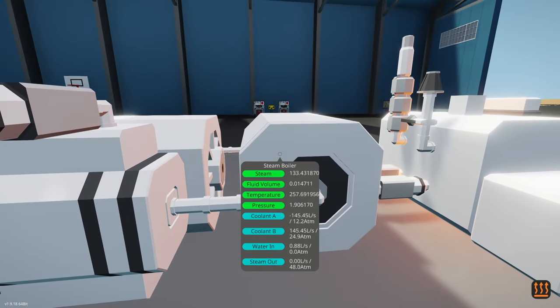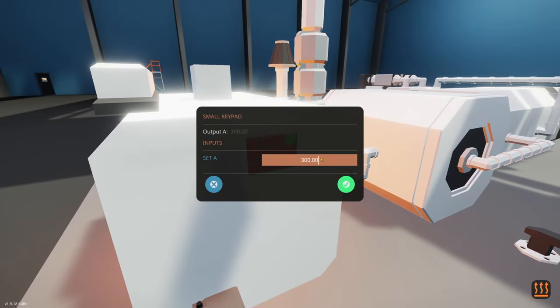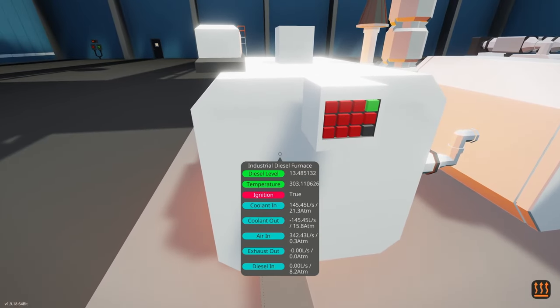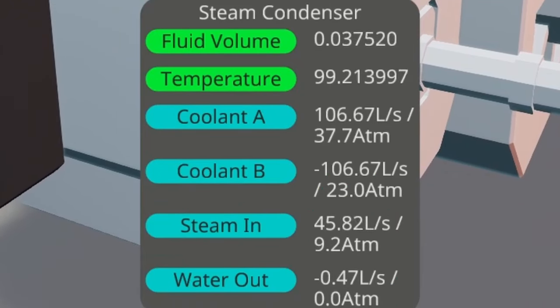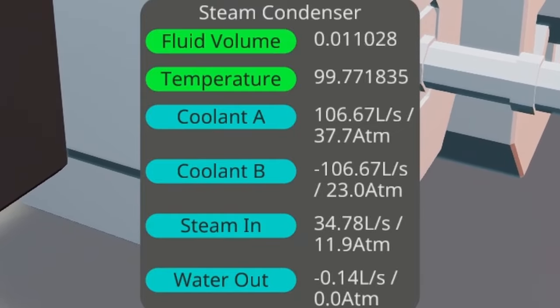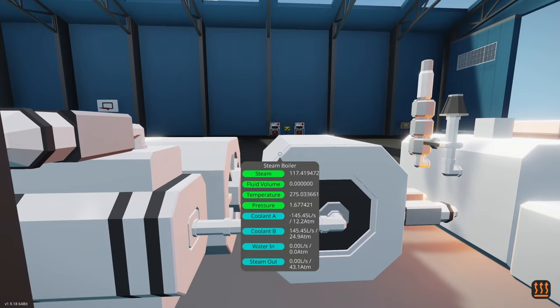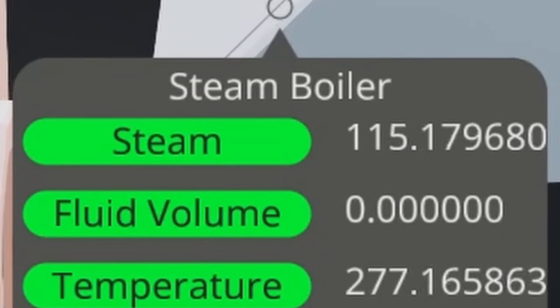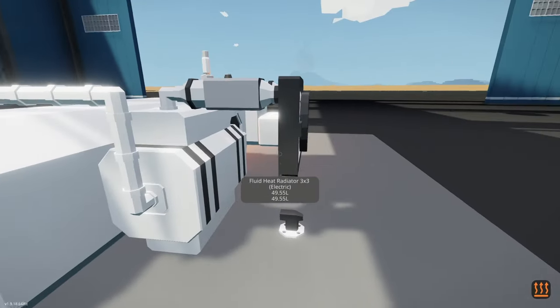We're putting a ton of heat into our room that would literally kill us. If we look at our boiler now, we're taking in 0.88 liters per second of water. Watch what happens when this condenser goes over 100 degrees — it's getting close. Let's increase this to 400 degrees. The condenser is up to 98.7 — once it hits 100, that steam is no longer going to be able to condense. The water coming out was 0.88, now we're at 0.44 — we're losing the amount of water we're making. Once we hit 100, we're not going to make any more water. The condenser cannot work above 100 degrees. Look at our fluid volume — it went to zero. Watch our steam go down. If we don't have water, we cannot make steam. And if we lose our steam, there goes our power. So I think this is a lot of the problem people are having.